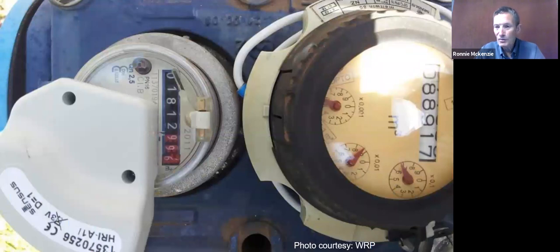When it comes to meters, again, every country has a different philosophy regarding meters. Just be careful when you're using loggers that if it's a combination meter, remember to log both meter heads and add them together. Sounds very basic, that, but you'll be surprised how often it doesn't happen.